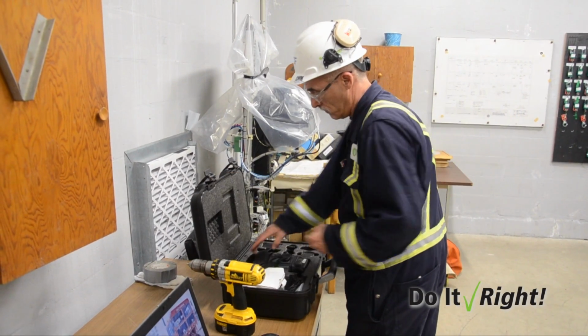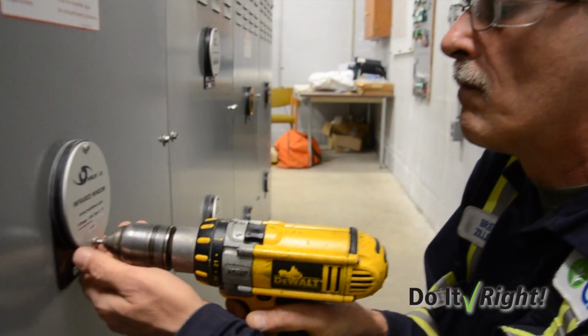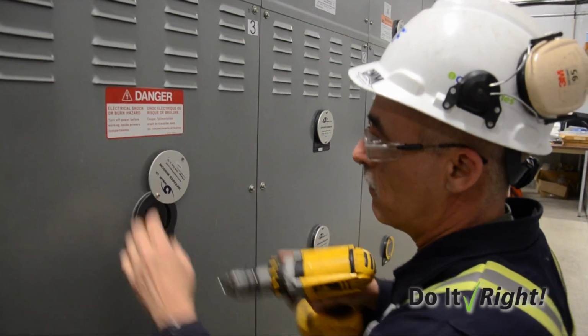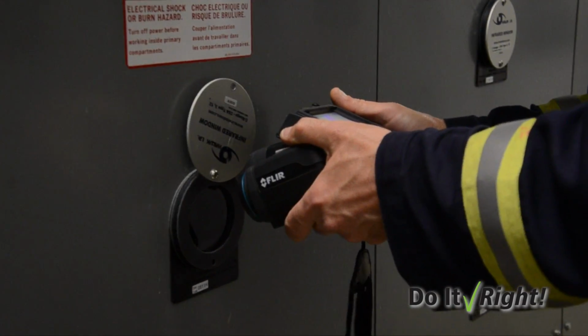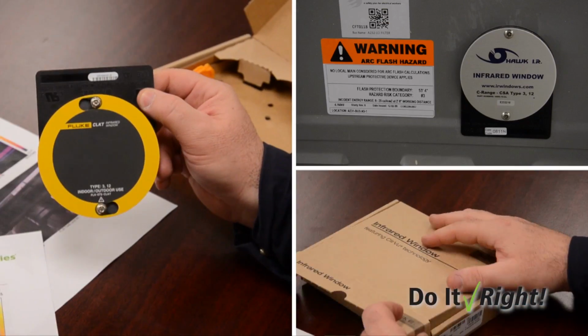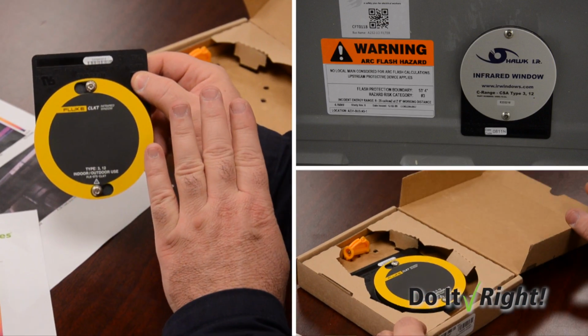The concept of the IR scan window is to allow for scans to occur without actually having to open up and physically scan the cabling with current running through the cable. It's a matter of opening the window, taking a look through, and it eliminates the exposure completely. We purchased a small number of windows, put them in some of our higher risk spots that we knew that we wanted to keep an eye on.